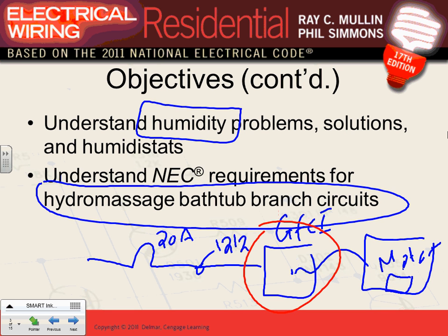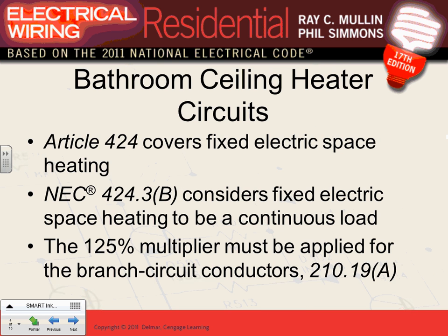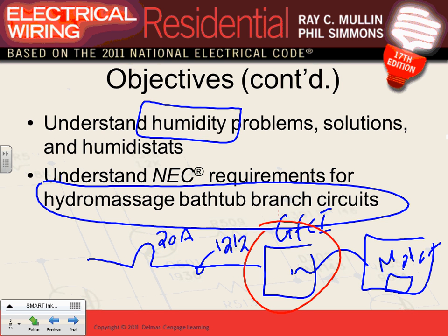That's why when we have a hydromassage bathtub, we don't put the GFCI right underneath the hydromassage bathtub, right? Why? Because my wife does not know how to use a screwdriver to take the panel off and get access and push that button. So the smarter ones put a regular receptacle down there under the hydromassage bathtub and a trip face. It looks like a receptacle, but it's really just a GFCI electronic trip face. You put it in the wall. So that's very typical with a hydromassage bathtub. Can I have thumbs up, Chad? Okay. That's basically it, go ahead. For that, would you need another one, because most of them come with heaters?